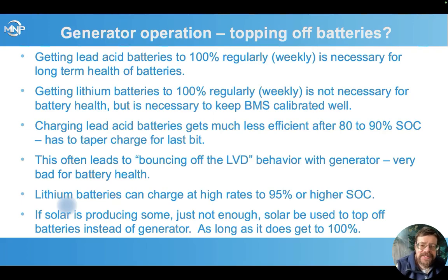For lead acid batteries, getting them to this 100% regularly with the generator was really pretty obnoxious, because after about 80% to maybe 90%, depending on the temperature of the battery and the particular type, they would hit full voltage and you'd have to taper charge for another several hours to get them all the way to 100%. And that led to much longer generator run times and less efficient use of the generator as we really started tapering down and not using the full capacity.